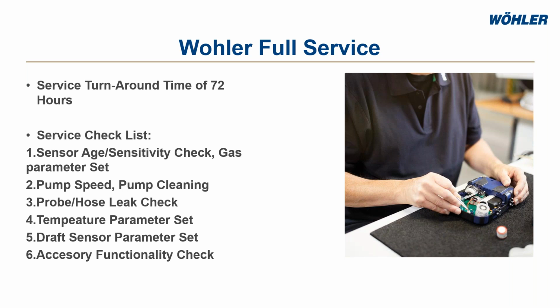First of all, they're going to check the sensor age. So there's some sensors in the analyzer, including the O2 sensor, which need replaced over time. So they're going to check the age to make sure that they're within the age requirement. They're going to check the sensitivity level on the sensors, and then they're going to set the gas parameter. So that's what really calibration means. They're going to run gas through it and make sure that the sensor recognizes, for example, what 100 parts per million of CO or 1,000 parts per million of CO would look like.